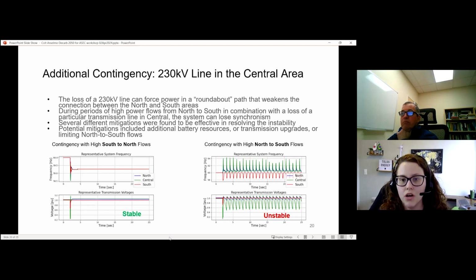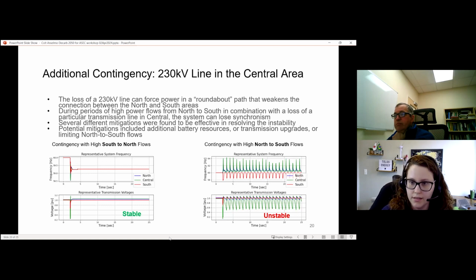So we are able to mitigate all of this loss of synchronism and these oscillations you see here with a battery. Another option would be transmission upgrades to provide a new path for power, so the power would not be forced into that weak connection between north, central, and south. And there is another option for that, because as I mentioned, the flow central to south on the Kenai intertie just happens in a very few hours of the year. So we can restrict the flow on this intertie and be able to mitigate the problem if we lose that line.